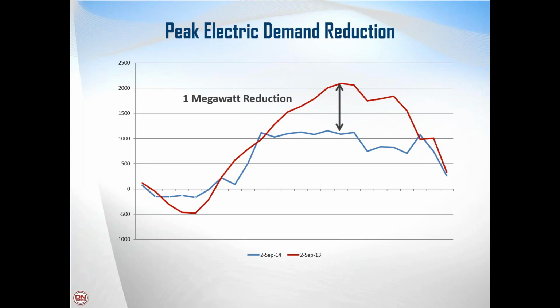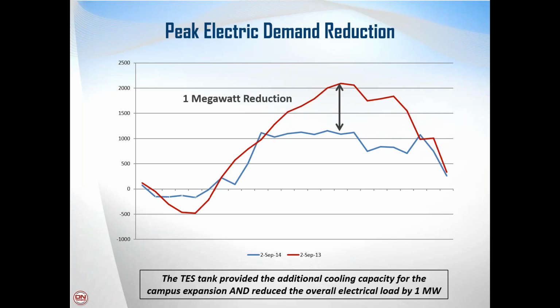The blue line represents the electric load after the thermal storage tank was added to their central plant. The red line represents the electric load prior to having their thermal storage tank. So you can see that they had a permanent electric load reduction of 1 megawatt of power, after they added their thermal storage tank, and the tank and the cooling water that was stored in there provided that additional cooling capacity for their expansion. So it provided the cooling for the expansion without adding more chillers and permanently reduced their electric load.